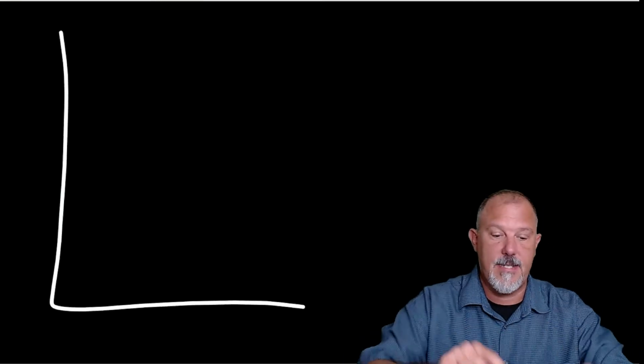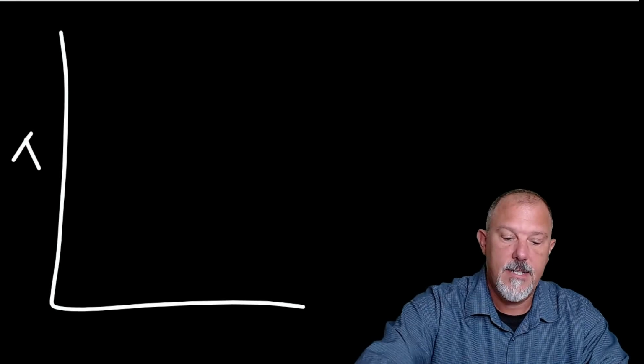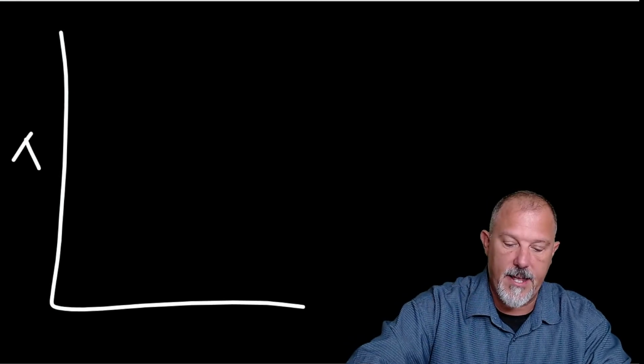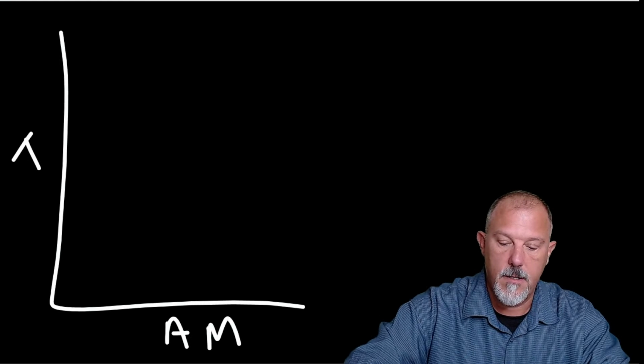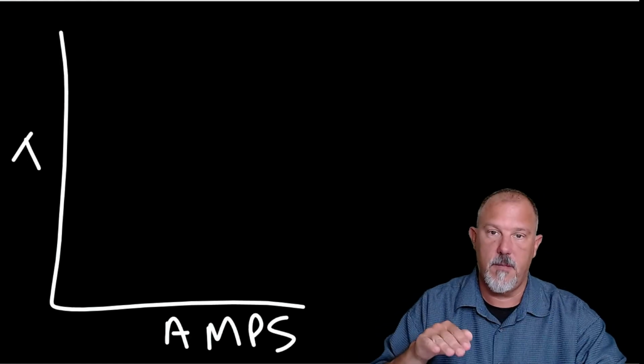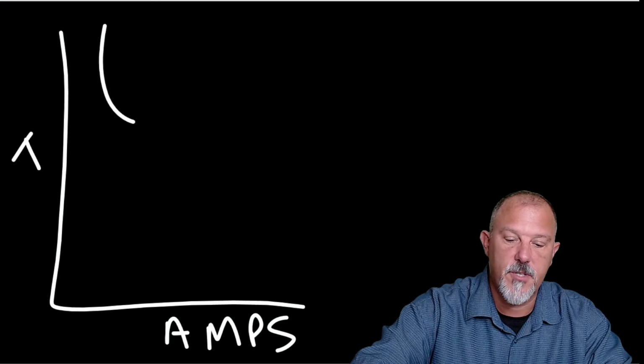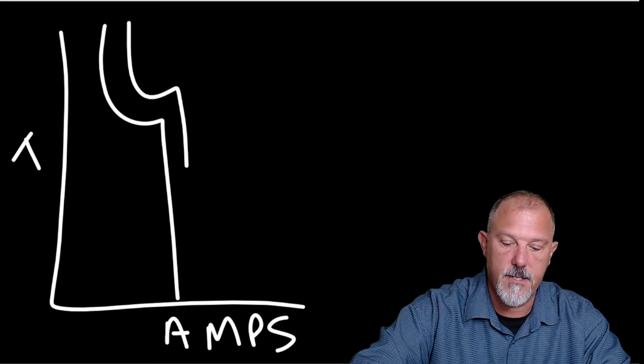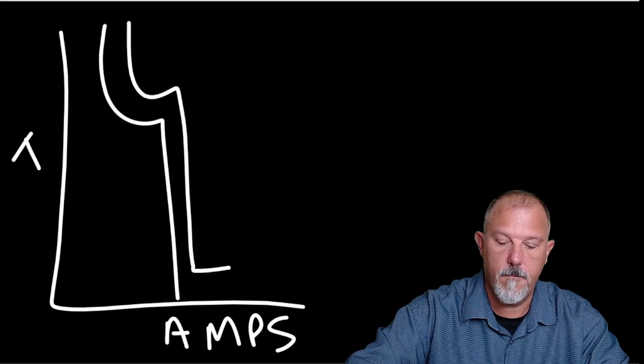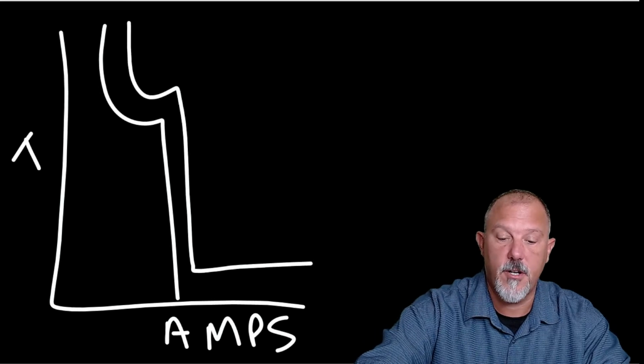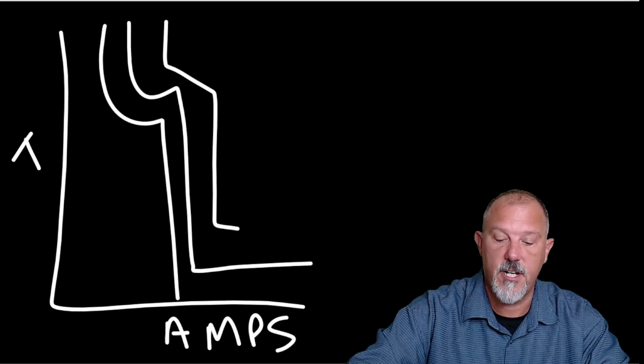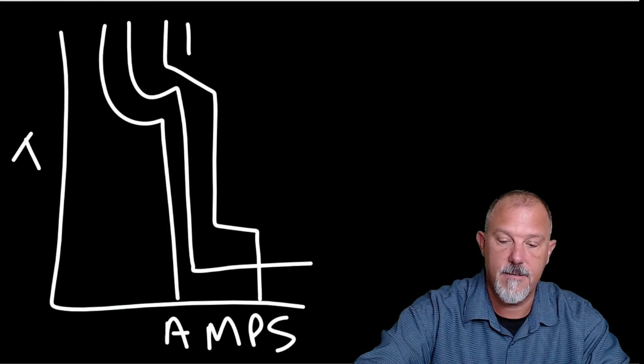What I want to do is give you what we're talking about. If you think about the time current characteristic curve, I have a TCC. I've got time up the axis and amps across the bottom. If I have a downstream circuit breaker that looks like this, and I have an upstream circuit breaker, and I'll make this an electronic trip unit that looks like that.